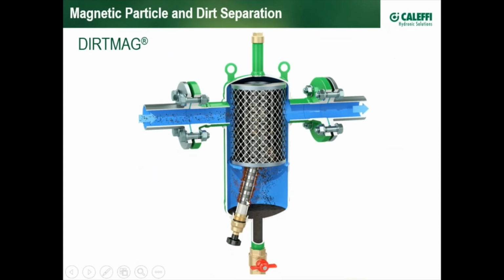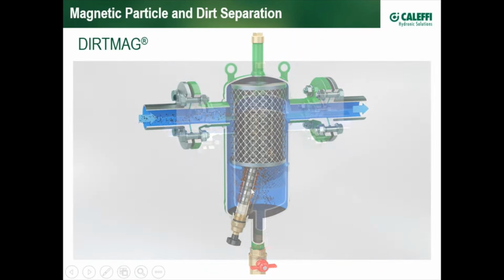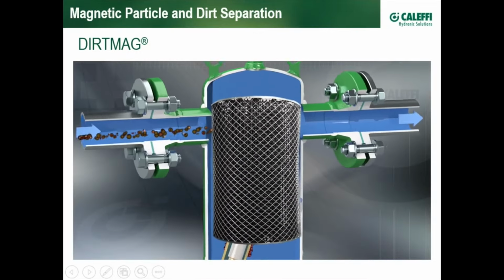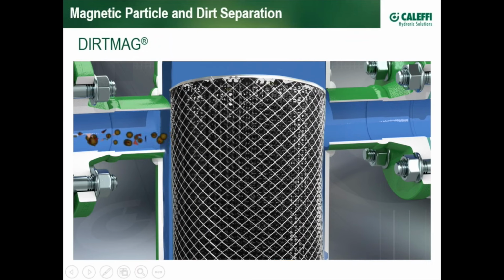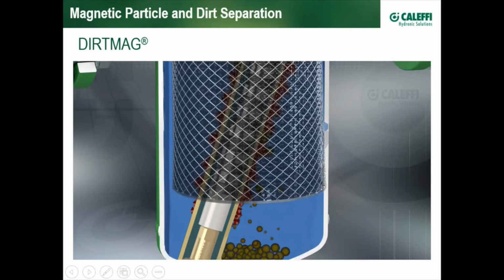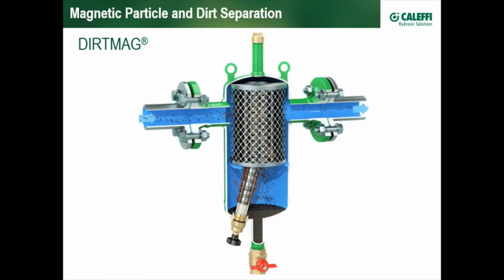So the magnetic stack, if you will, of rare earth magnets, same technology used by the pump guys, we employ to attract ferrous oxide. Debris comes in, the debris that's not ferrous slows down, gets deflected by the mesh, drops into the bottom, and debris that is magnetic and in the past problematic, that would have a chance to pass through and find its way into the system where it shouldn't, create problems, the magnets attract it to the brass sleeve, only for the contractor then to eventually drain down, as you see here. He can pull the bayonet out. It's a dry well, by the way. All the debris drops to the bottom, and then the purge valve can be opened here. This shows it cracked here. This is basically by design, because if the separator was placed close to the floor, you'd run into interference with the floor when trying to pull the bayonet down.